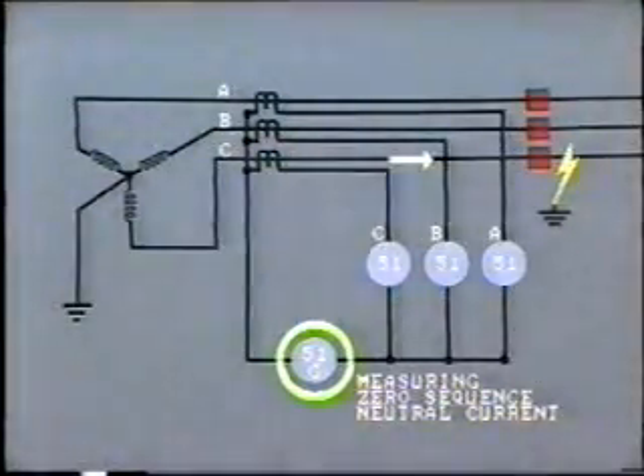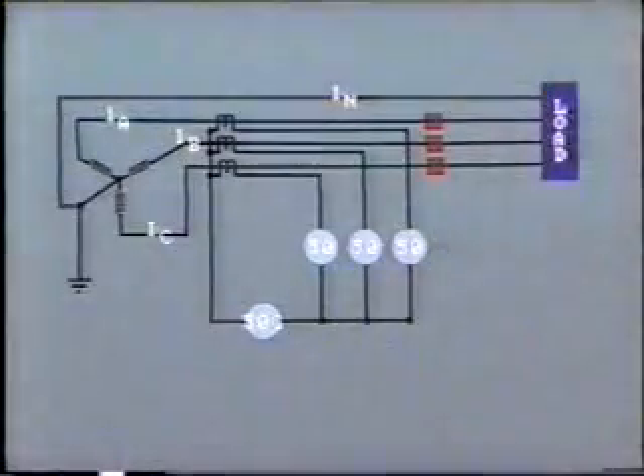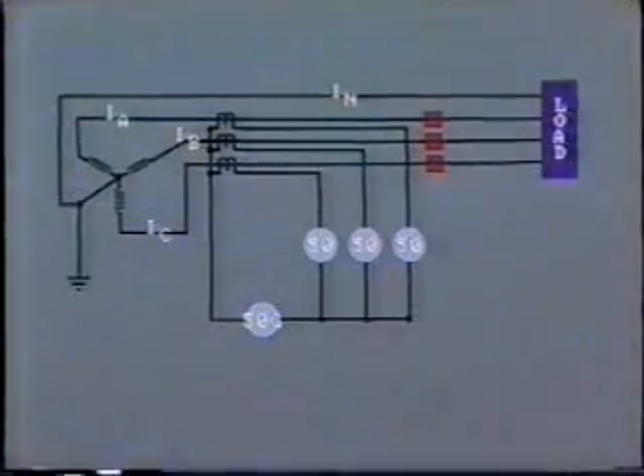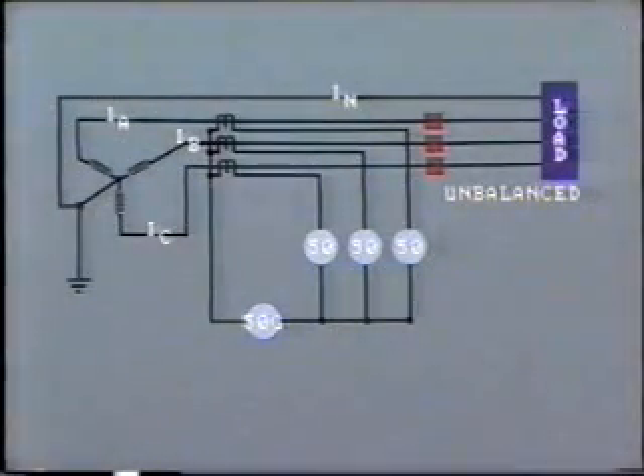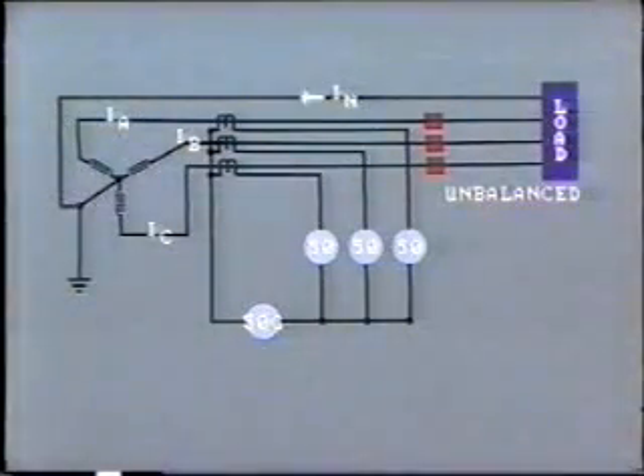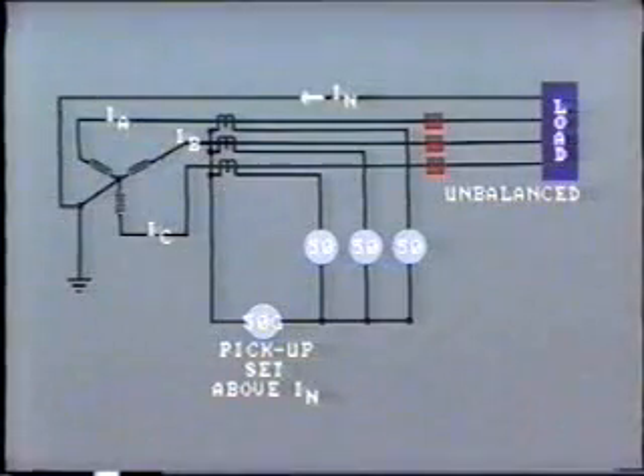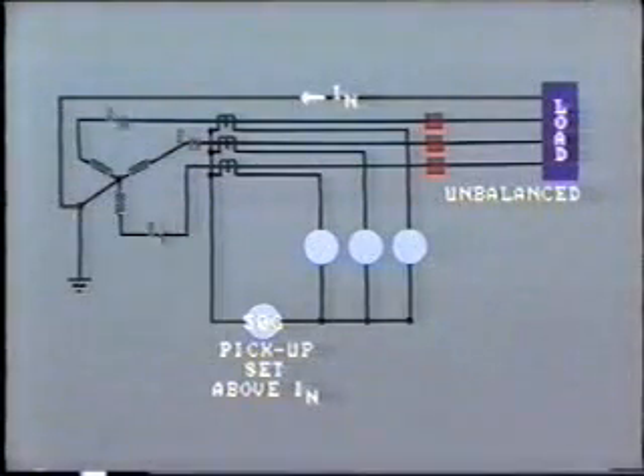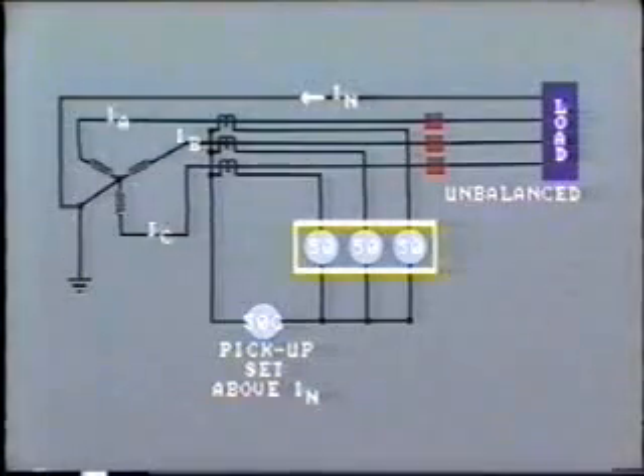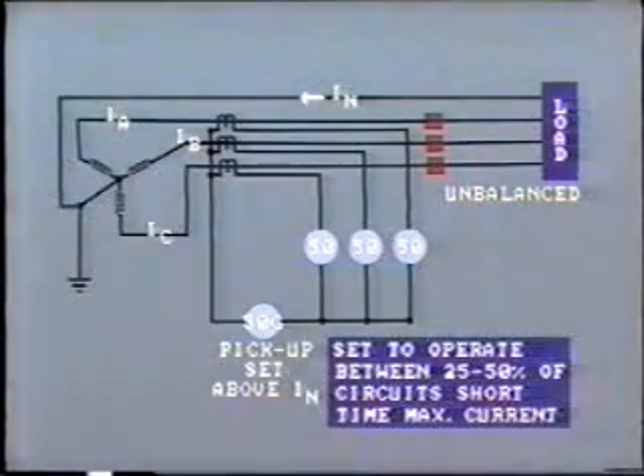In setting the pickup for this relay, we must bear in mind the type of circuit in which it is installed. For example, if this is a radial distribution line, then it is probable that there is a certain amount of unbalanced load during normal operation, resulting in current flow through the neutral. Obviously, the relay pickup must be set above this value. On the other hand, there is no need to set the pickup above the level of load current flowing through the conductors, as is the case with a phase relay setting. In order to accommodate these factors, the relay is usually set to operate at between 25 to 50% of the circuit's short-time maximum current.